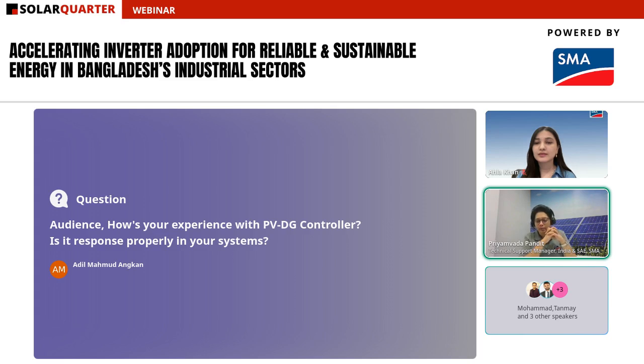Also reactive power management, because if most of your active power is taken over by PV, the reactive power requirement would be fulfilled only by the DG, and then your DGs would operate at a very bad power factor, with poor efficiency—consuming a lot of fuel even at very low operating power. All this needs to be taken into account, and the hybrid controllers we offer include reactive power management and management of spinning reserve demand across multiple diesel gensets. So apart from reverse power protection, all this is already included in our offering, which is why we typically mention it.